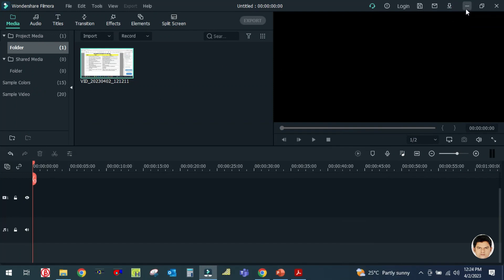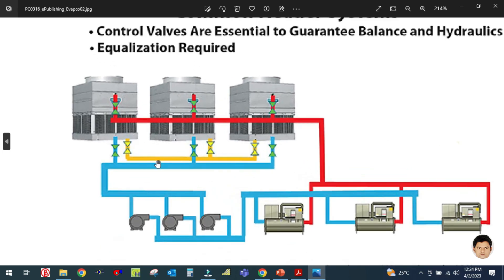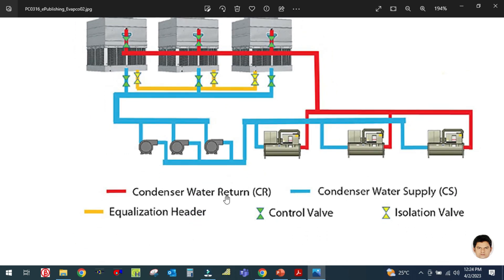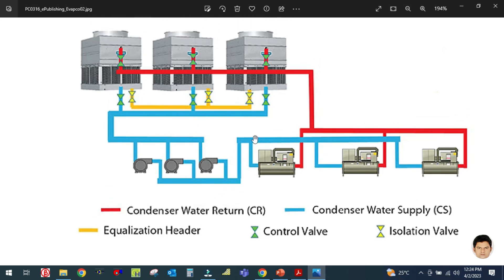You can see here this is the cooling tower, this is the condenser water pipe, and this is the condenser water pump. The red color is condenser water return and the blue color is condenser water supply. The condenser water takes water from the chiller condenser and sends it to the cooling tower, and from the cooling tower it returns back to the chiller. This cooling tower and condenser water pump system is not required in an air cooled chiller.